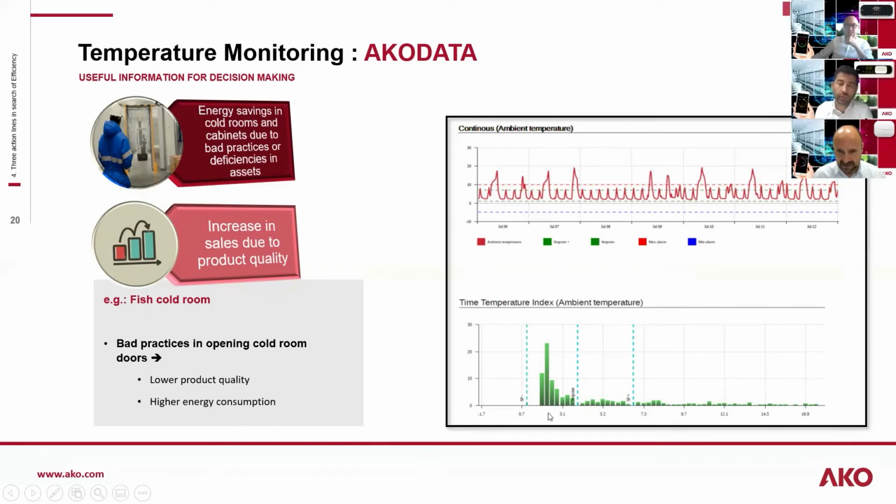So most of the time, the cold room is in the minimum temperature area, and we have this prolongation or extension of the temperatures to the positive side. These are the continuous door openings during the day. So finally, we have detected a bad practice.